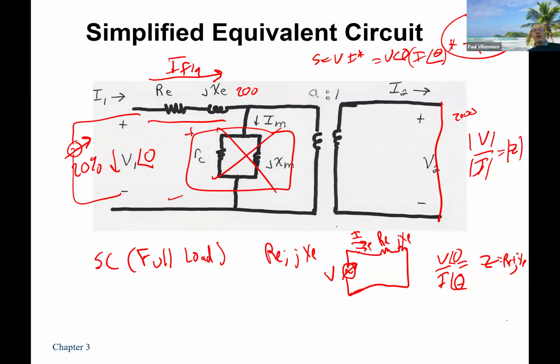How do you think you would measure or solve for R_c and jX_m? Remember, make them important. Ramp up the voltage and then do what with the current? Yeah, make the current so small that the voltage drop that we have across R_e and jX_e is negligible, and take the voltage as high as possible. What kind of a configuration would give you a high voltage and no current? An open circuit test. So my open circuit or no load, sometimes this is called no load loss too, is it going to give us the R_c and the jX_m?